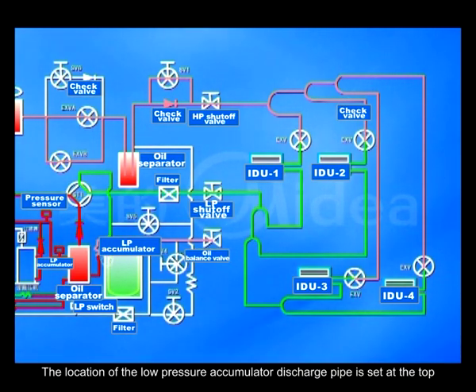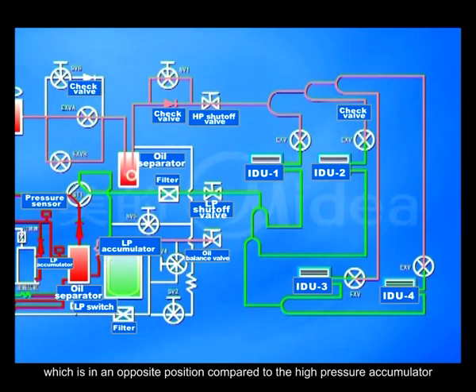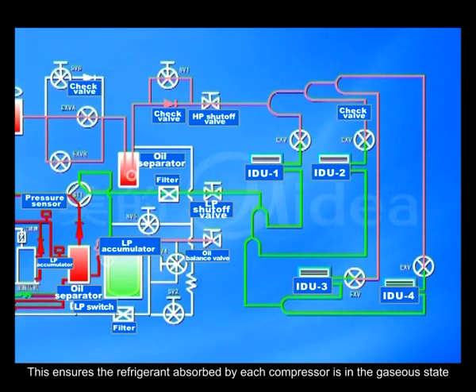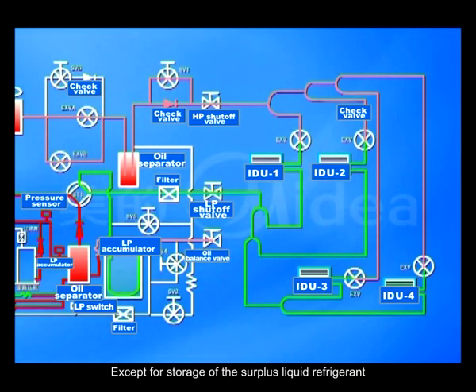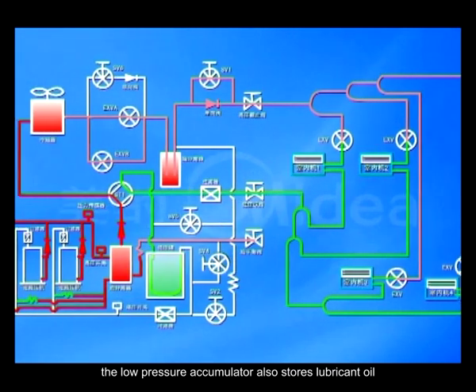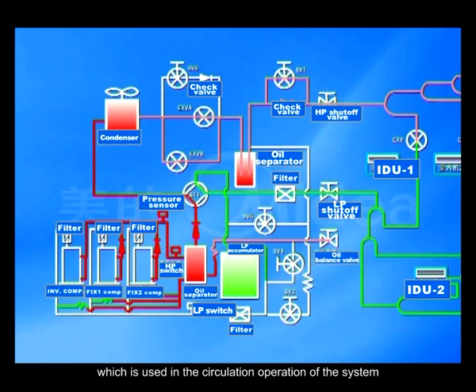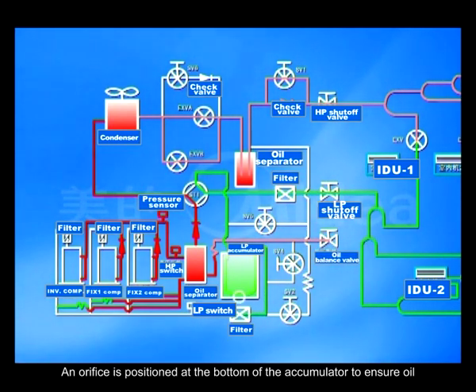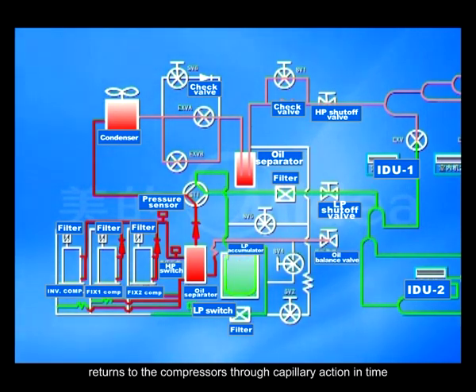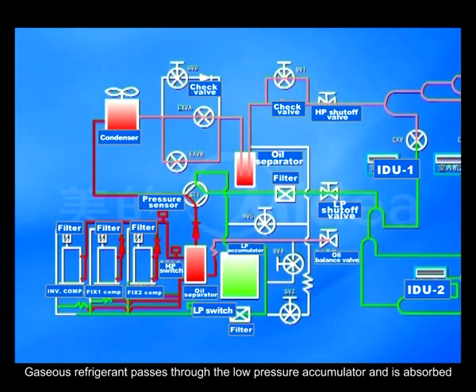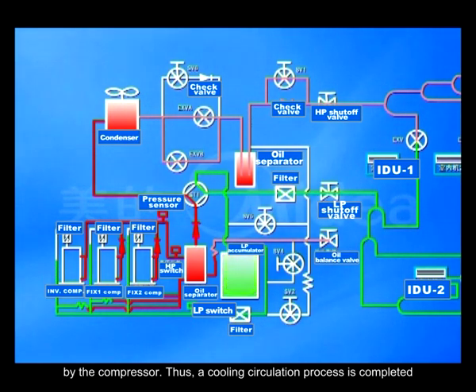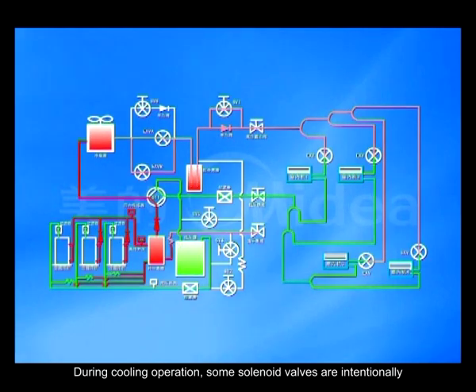The location of the low-pressure accumulator discharge pipe is set at the top, which is in an opposite position compared to the high-pressure accumulator. This ensures the refrigerant absorbed by each compressor is in its gaseous state. Except for storage of the surplus liquid refrigerant, the low-pressure accumulator also stores lubricant oil, which is used in the circulation operation of the system. An orifice is positioned at the bottom of the accumulator to ensure oil returns to the compressors through capillary action in time. Gaseous refrigerant passes through the low-pressure accumulator and is absorbed by the compressor. Thus, a cooling circulation process is completed. During cooling operation, some solenoid valves are intentionally equipped to make sure the system operates under the optimum state.